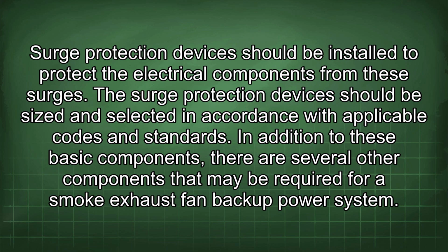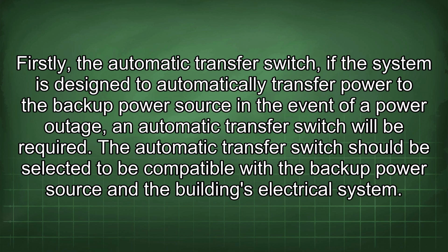In addition to these basic components, there are several other components that may be required for a smoke exhaust fan backup power system. Firstly, the automatic transfer switch. If the system is designed to automatically transfer power to the backup power source in the event of a power outage, an automatic transfer switch will be required. The automatic transfer switch should be selected to be compatible with the backup power source and the building's electrical system.